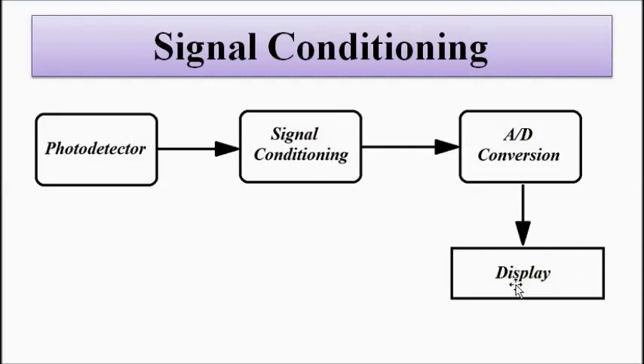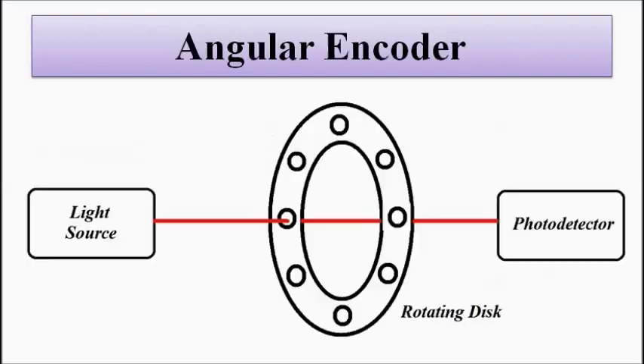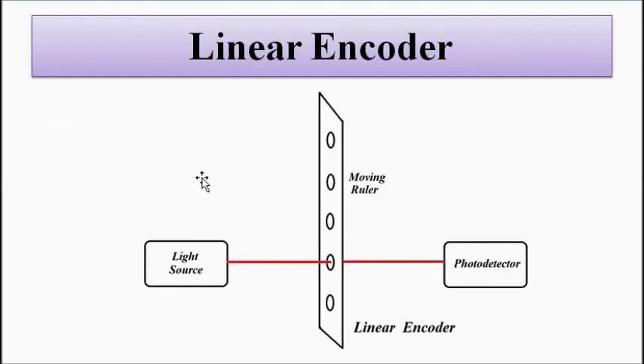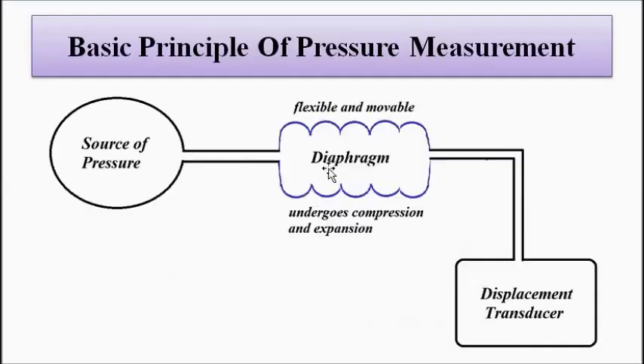Where the measurement of the blood pressure in terms of the relevant units is displayed. So here we are using the angular encoder or the linear encoder which is acting as a secondary sensing element. The primary sensing element is diaphragm which is responding to blood pressure fluctuations.